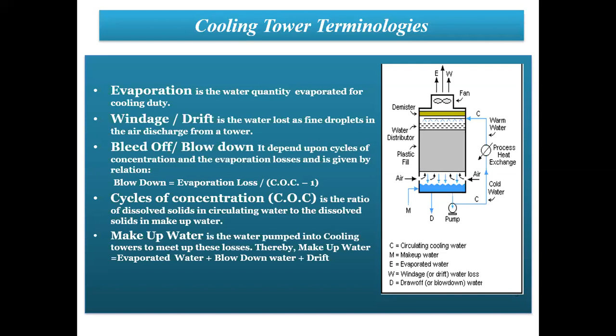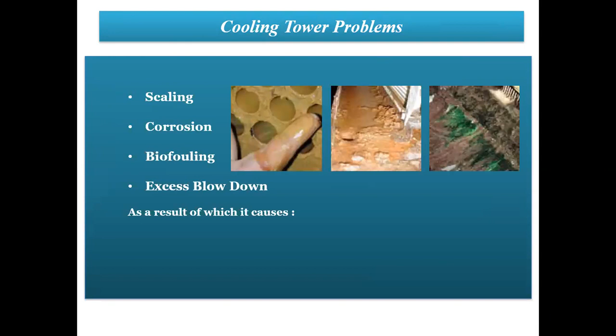So what are the cooling tower problems we generally face? There are 3 or 4 major problems which are being faced in the cooling towers. The first one is obviously the scaling. The first picture also shows that it's a deposition of calcium carbonate, which precipitates in fine layers in your condenser tubes, in the whole condenser loop actually.